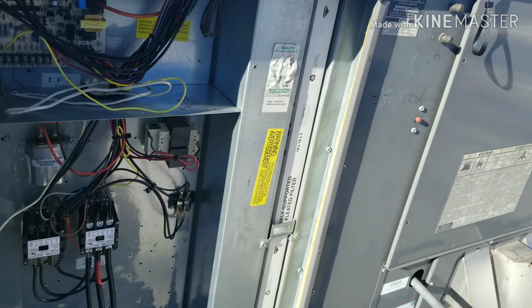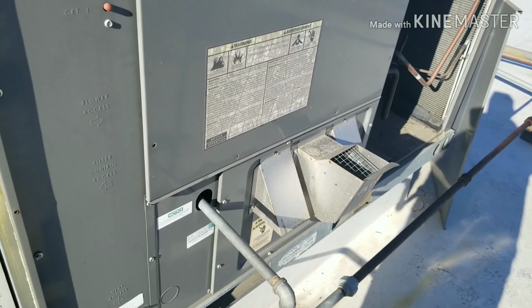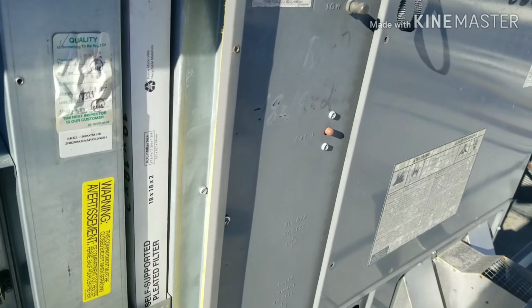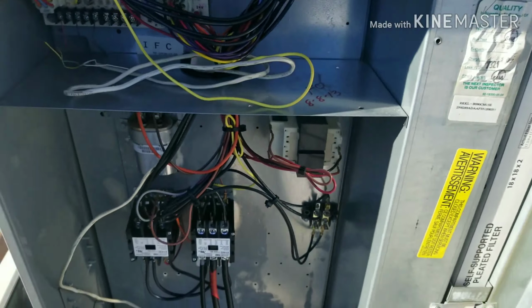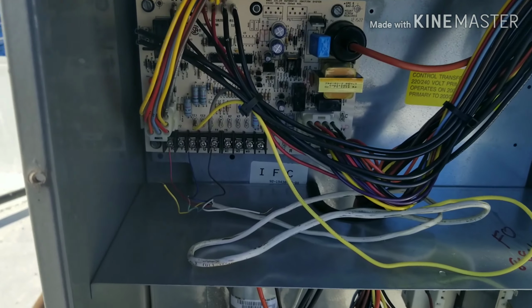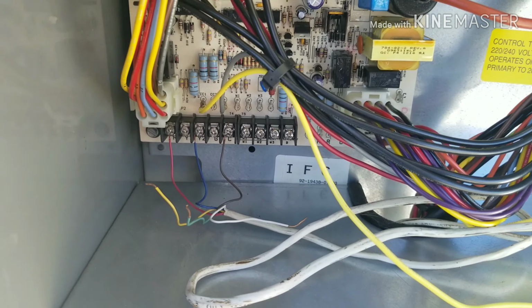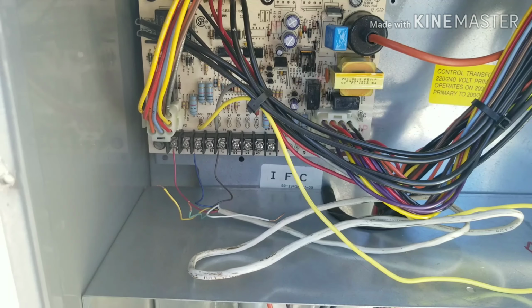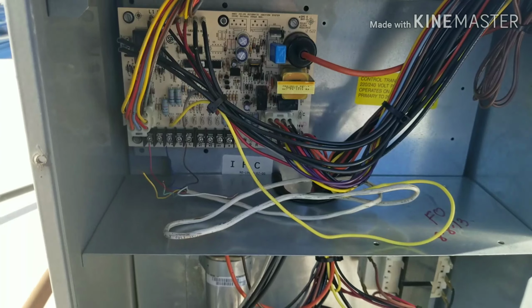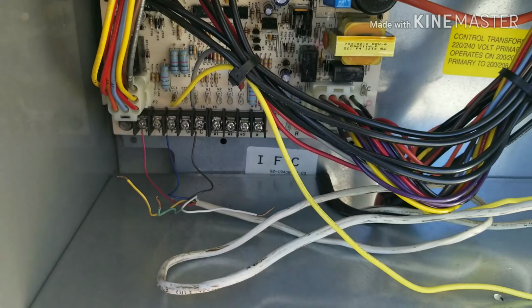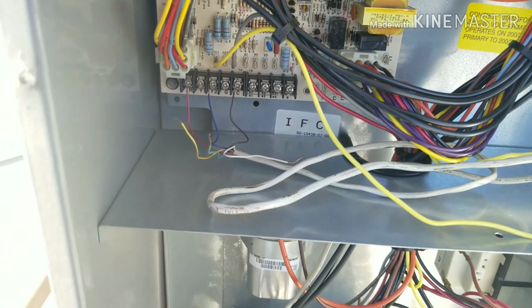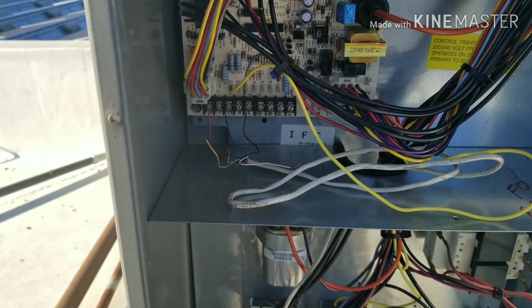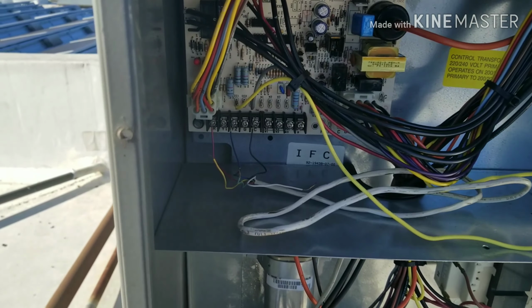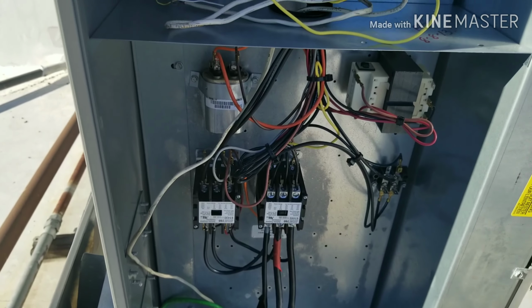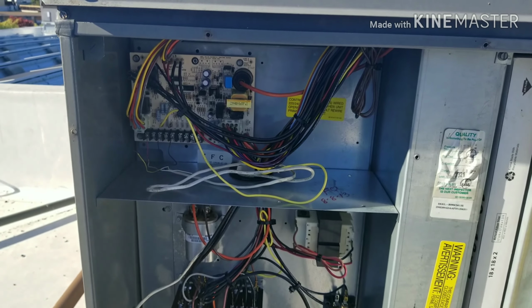Alright guys, well there you have it. These are turned off. The indoor fan blower is still on. Remember to remove the thermostat wires when you're jumping these things, because you don't want someone downstairs to turn on the AC while you're testing on the heat, and then it might ruin the thermostat or your board. So make sure you remove them and let your tenants know that you're going to be troubleshooting, not to touch the thermostat.